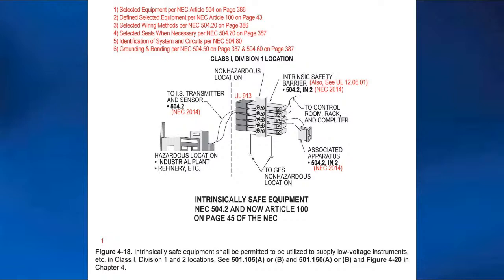Where would that be at, or what would that be? Which kind of cable now? Like an intrinsically safe cable. Is there some kind of color marking on the cable? It would be listed if it was specifically designed for that, just like non-incendive. You can get a non-incendive wiring method, but you can still use tray cable if you wanted to for non-incendive, and you can use any of the wiring methods here. You do not have to go to a listed intrinsically safe cable. Okay. And you can read that for yourself in 504.20. It's very clear there. 10-4.